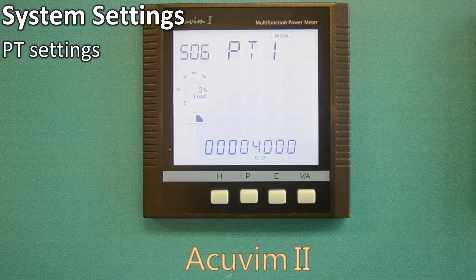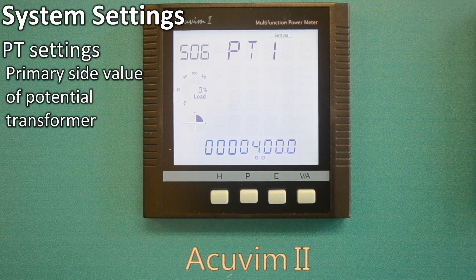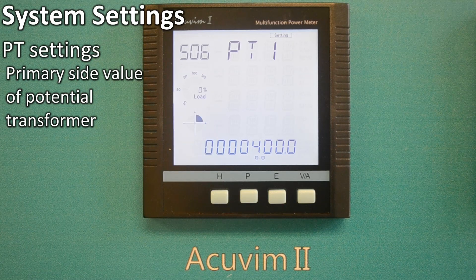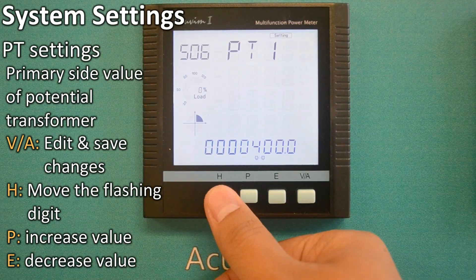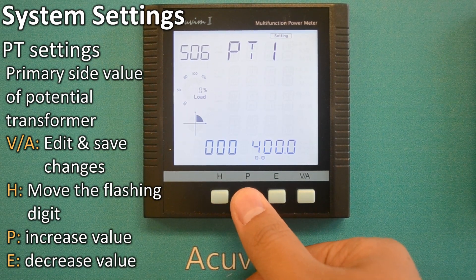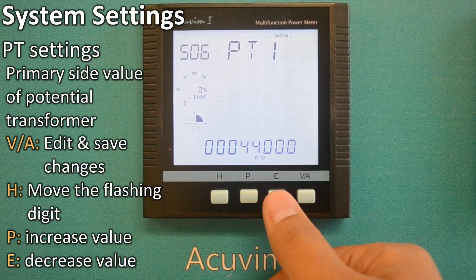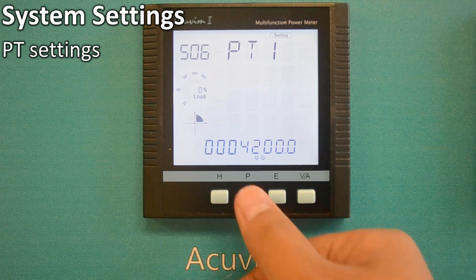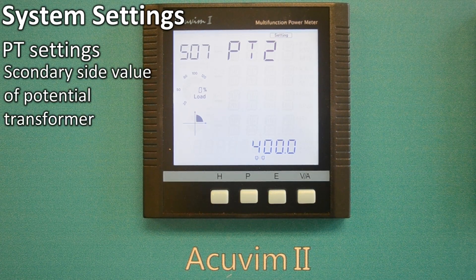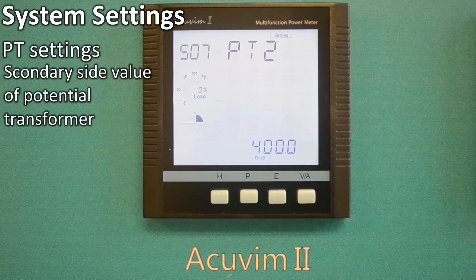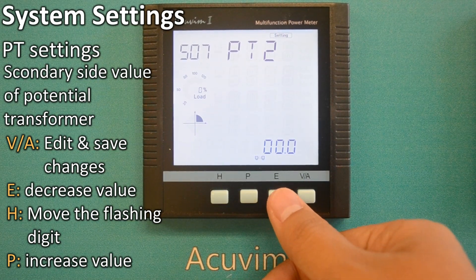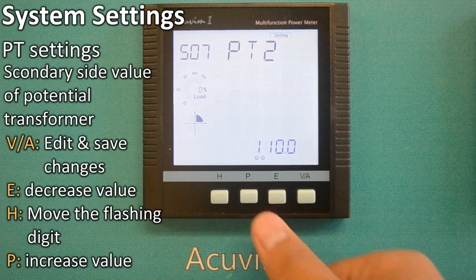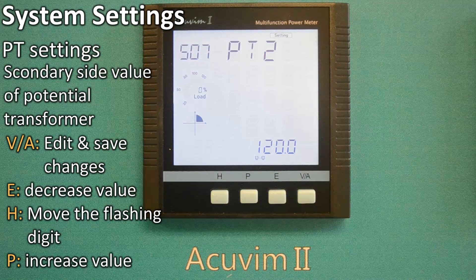PT1 400 means the primary side value of the potential transformer. For example, if a 4200 to 120 volt transformer is used, PT1 should be 4200 volts. To make a change, press VA and the setting will flash, indicating it is ready for editing. Press H to move the flashing digit, press P to increase or press E to decrease the value, making the change, for example, to 4200. Pressing VA will then save the change. PT2 400V indicates the secondary side value of the potential transformer. In this case, we are changing it to 120 volts and the same PT setting process applies. If you do not have a potential transformer, simply leave PT1 and PT2 at the factory settings of 400.